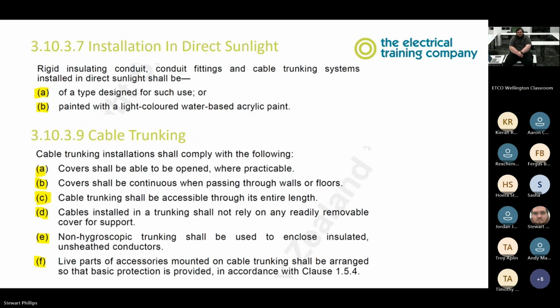Trunking. So trunking installations shall comply with the following. Covers shall be able to be opened where practicable. Covers shall be continuous when passing through walls or floors. So if we have a piece of trunking that goes through a wall, that cover must be continuous. If it goes through a floor, it must be a continuous cover. The trunking shall be accessible through its entire length. Cables installed in trunking shall not rely on any readily removable covers for support, so we cannot use the cover as a form of support.